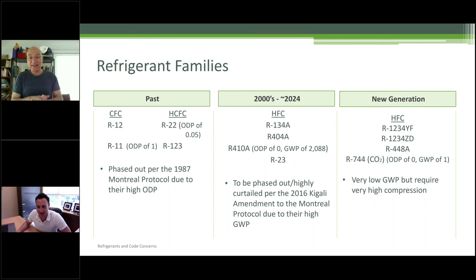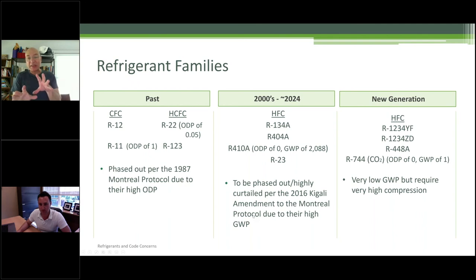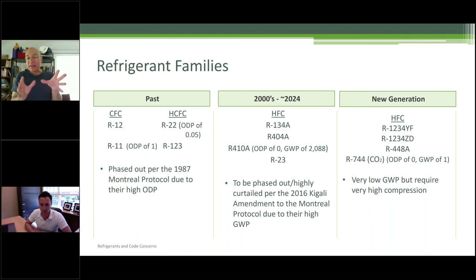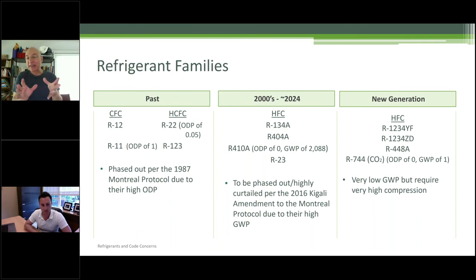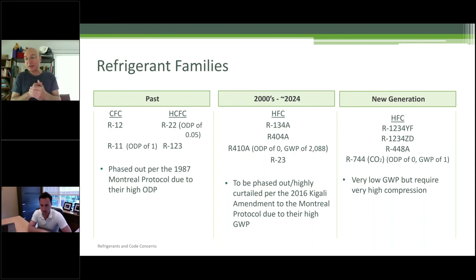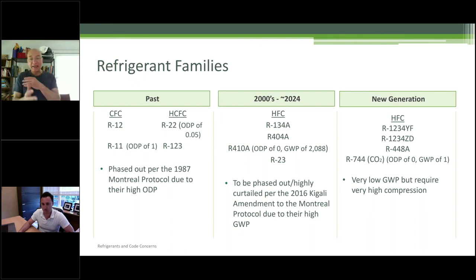Does the new code deal with flammability and the fire department? The new code really only added how to address VRF — we wanted to incorporate VRF technology into Chapter 11, which wasn't talked about at all before. This whole section of the code basically incorporated the arbitrary 10-pound rule in public corridors but didn't talk about occupied spaces. So these two sections are how it deals with VRF. For B refrigerants, B1, B2 — nothing else changed. We're still following the international code and ASHRAE for those.